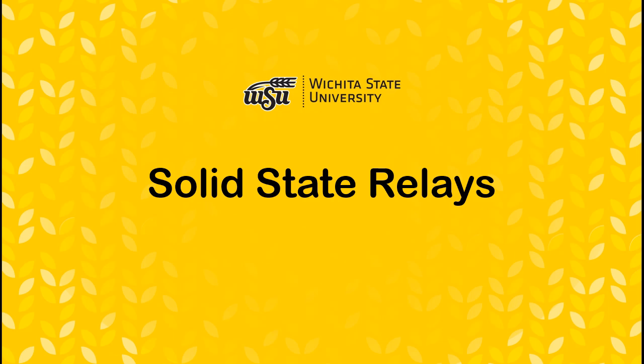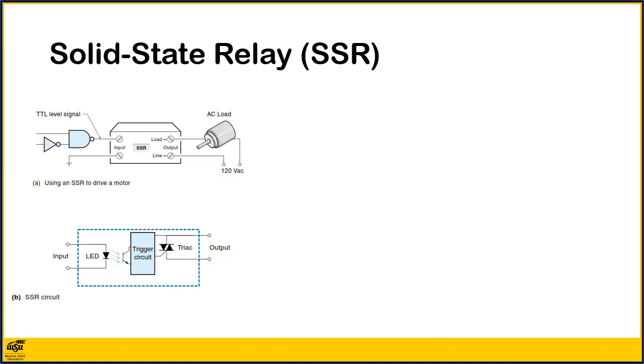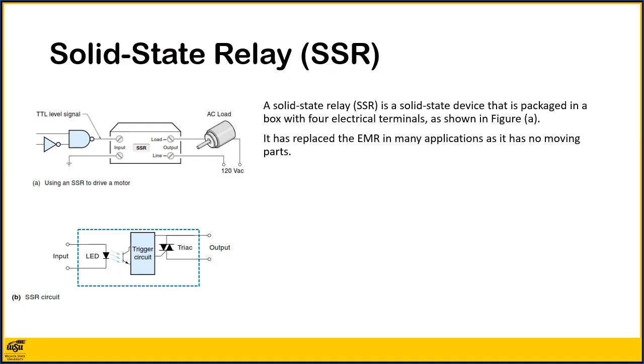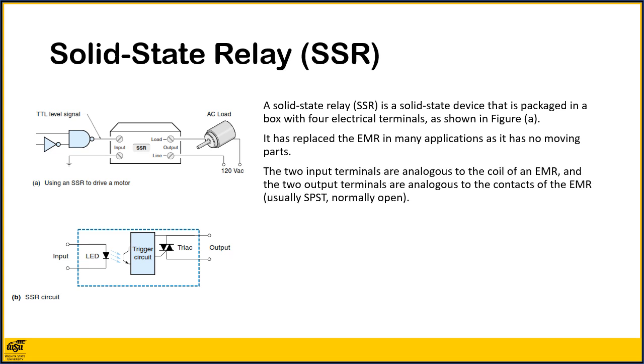We move on now to solid-state relays. A solid-state relay, SSR, is a purely solid-state device that has replaced the electromechanical relay in many applications, particularly for turning on and off AC loads such as motors. Physically, the SSR is packaged in a box about the same size as an EMR, with 4 electrical terminals as shown in Figure A. The 2 input terminals are analogous to the coil of an EMR, and the 2 output terminals are analogous to the contacts of the EMR, usually single pole, single throw, normally open.